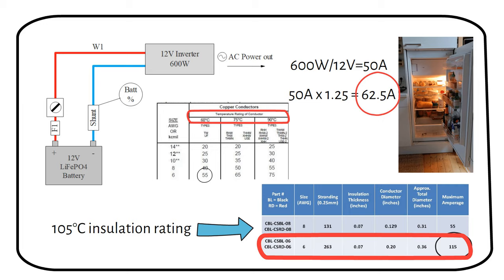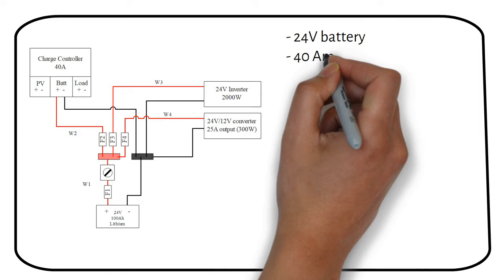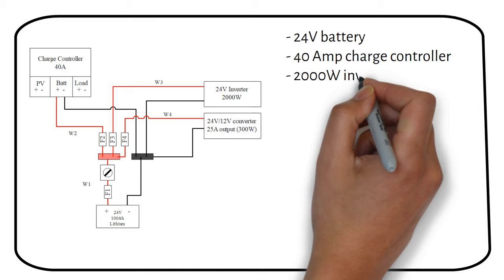Let's do a few other calculations for a client of mine. He has a 24 volt battery, a 40 amp charge controller, a 2000 watt inverter, and a 300 watt DC to DC converter. We will start by sizing the main cable which is called W1, coming from the battery.